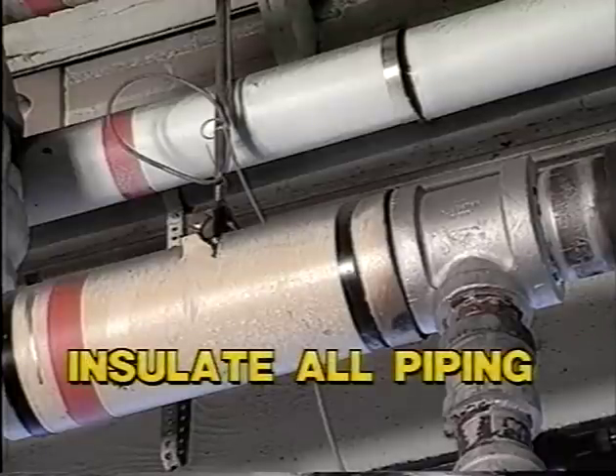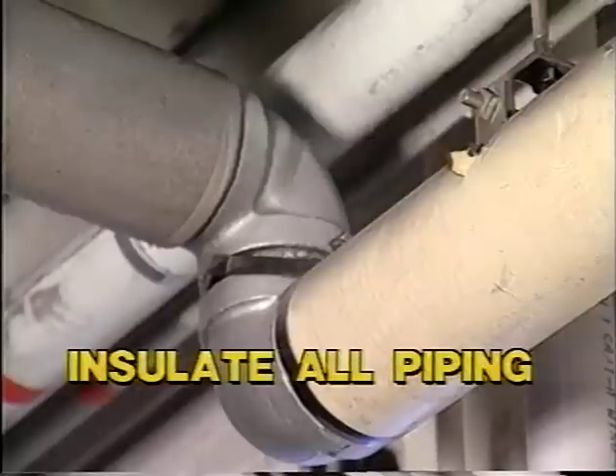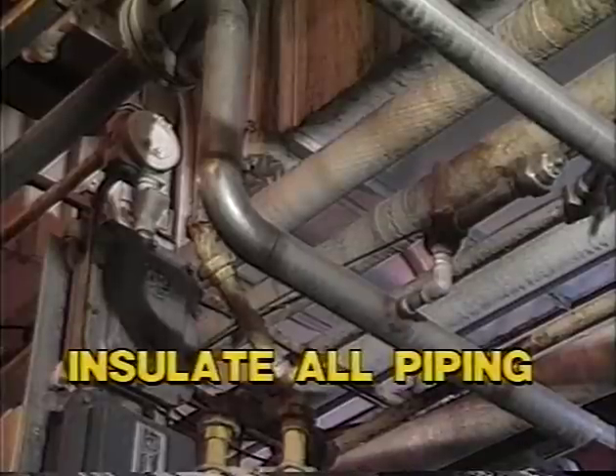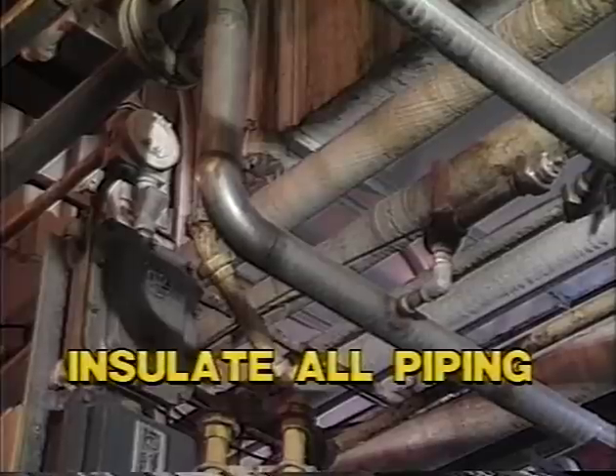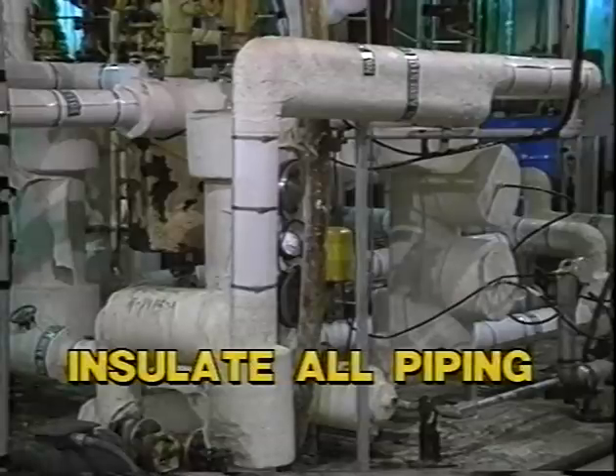In both of the two previous cases, the condensing of steam downstream of the seal produced the acceleration. It follows that the likelihood of differential shock arising and causing water hammer is greater in uninsulated pipes, especially on outdoor systems, than in insulated pipes.